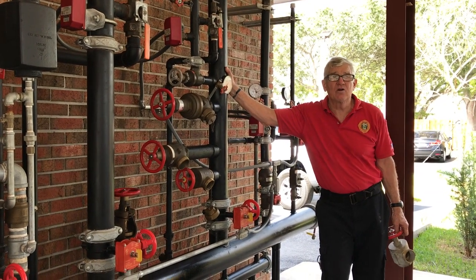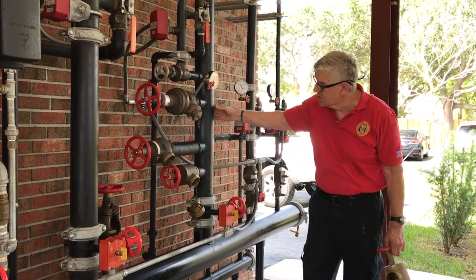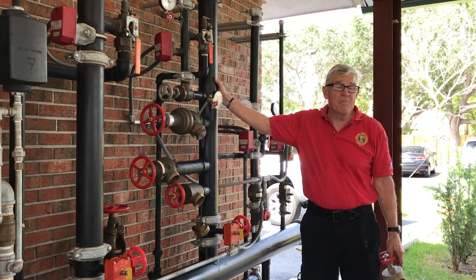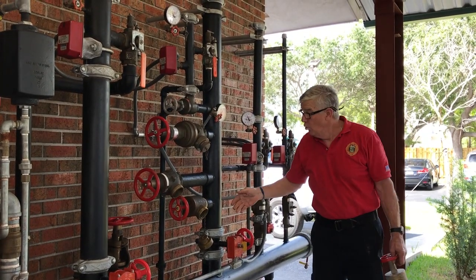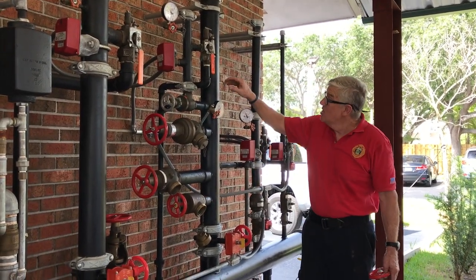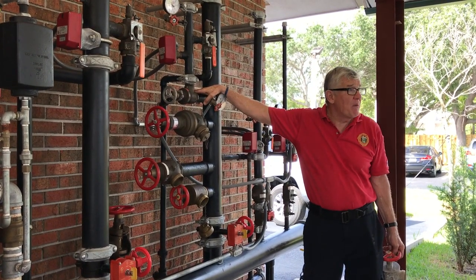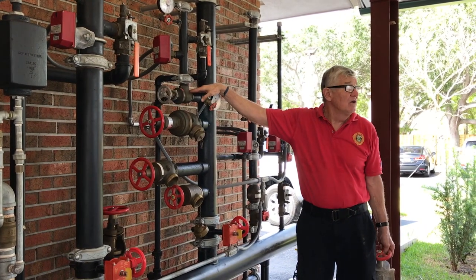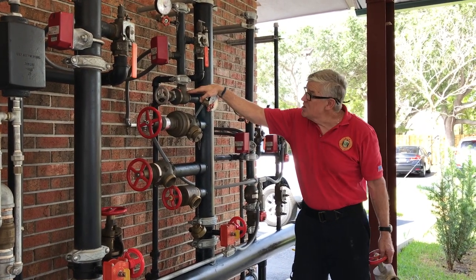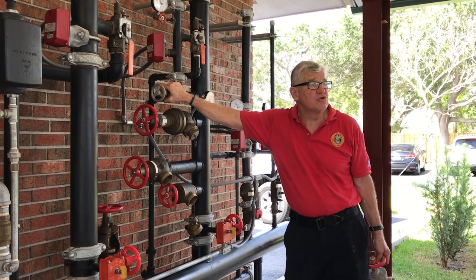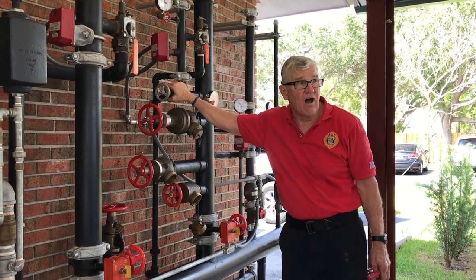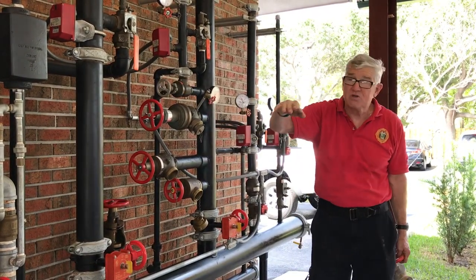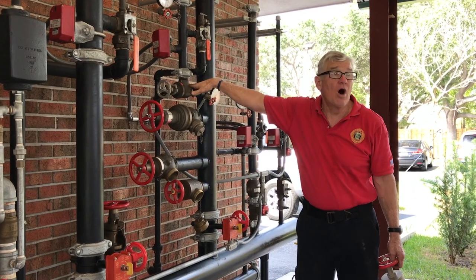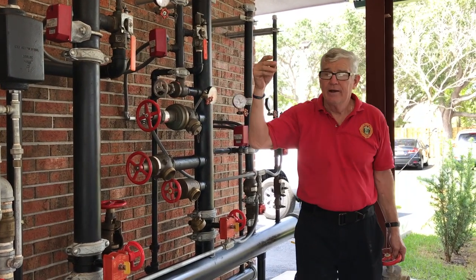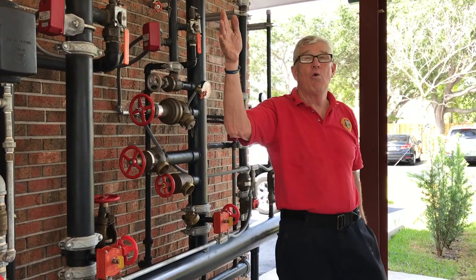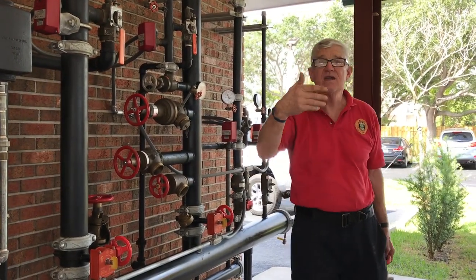Of a combination sprinkler and standpipe system, and this is the most common in our jurisdiction. In other words, we have a standpipe, typically one in each stairwell, with hose outlets for firefighting, and control valves for the sprinkler piping that branches off of the standpipe system. Now, on each floor, you'll have one or more we call floor control, zone control, or floor isolation valves. Some buildings, the systems are looped, so you will have more than one control valve. Others, it's odd floors, may be served by the west stairwell, even floors by the east stairwell.